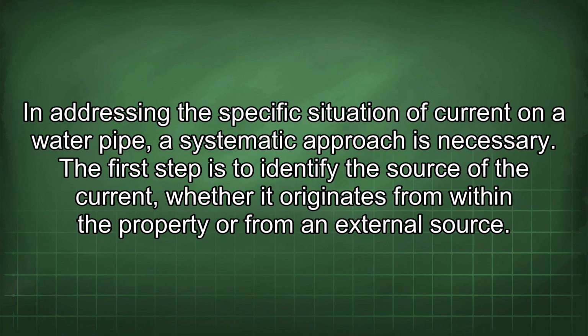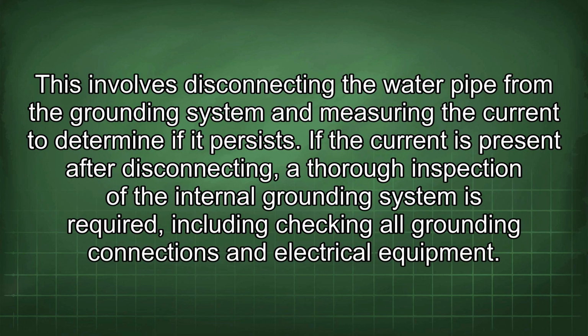In addressing the specific situation of current on a water pipe, a systematic approach is necessary. The first step is to identify the source of the current, whether it originates from within the property or from an external source. This involves disconnecting the water pipe from the grounding system and measuring the current to determine if it persists. If the current is present after disconnecting, a thorough inspection of the internal grounding system is required, including checking all grounding connections and electrical equipment.